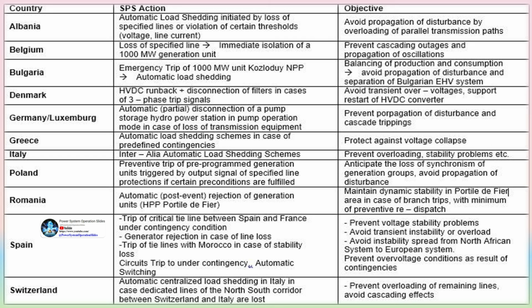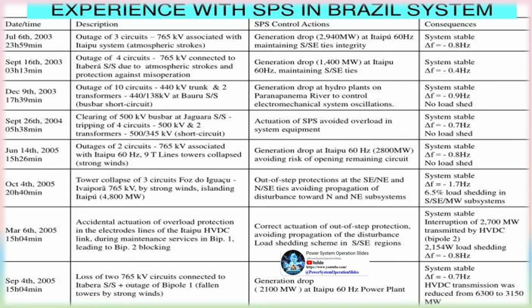Voltage instability: inability of the power system to maintain steady acceptable voltages at all buses in the system. Countermeasures: change of the generator voltage set point, automatic shunt switching, control of series compensation, blocking of tap changer of transformers, and under voltage load shedding. Transient angular instability: inability of the system to maintain synchronism. Countermeasures: braking resistor, FACTS devices, reducing the mechanical power driving the generator, fast valving, disconnection of the generator, etc. Oscillatory instability: lacks natural damping of oscillations. Countermeasures: tuning of PSS, FACTS devices.